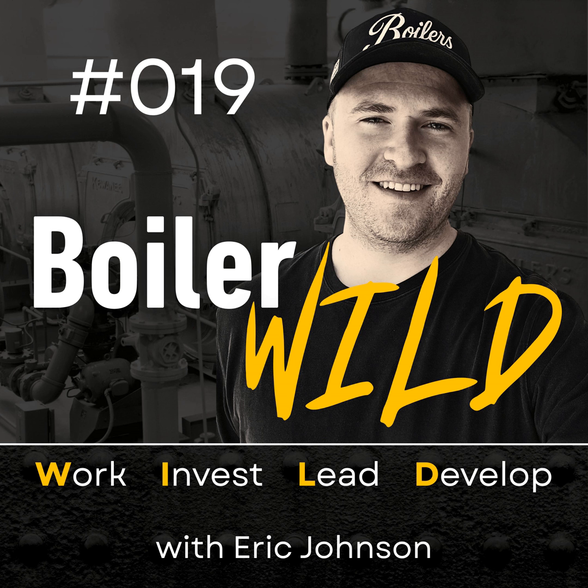I could talk about this for hours, but this goes on. There's all kinds of things that you can do to increase the efficiency of your hydronic system. And it very, very rarely comes down to what the marketed efficiency of your boiler is. The efficiency of your hydronic system is really going to play into how well the install is and how well the engineer sized the system, sized the boiler, and what your water flow is like, and what your water temperatures are.